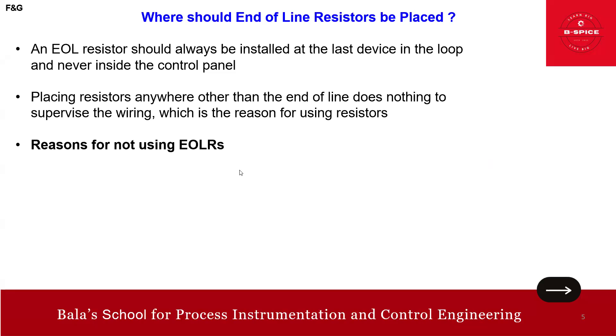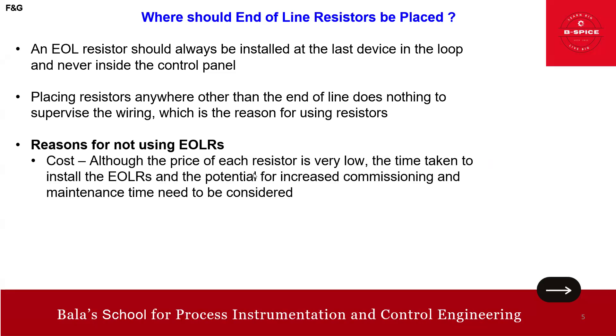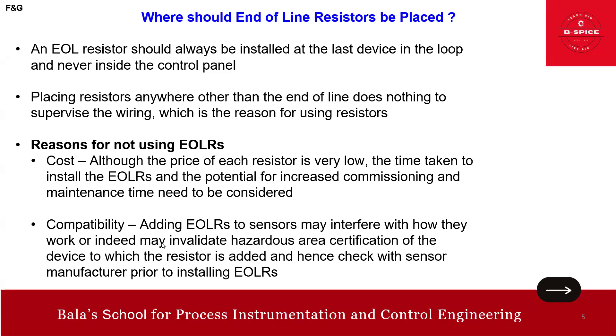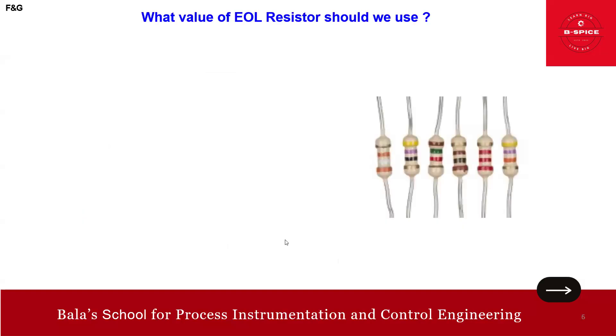Reasons for not using EOLR: although the price of each resistor is very low, the time taken to install EOLRs and the potential for increased commissioning and maintenance time needs to be considered. Second, compatibility — adding an EOLR to a sensor may interfere with how it works, or may invalidate the hazardous area certification of the device. Always check with the sensor manufacturer prior to installing.